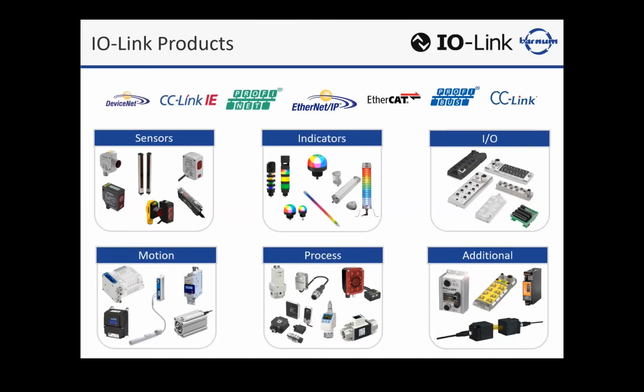So if we look at sensors themselves, having IO-Link capability allows you to program that sensor, set points, functionality directly from the HMI without necessarily a PC interface or changing your PLC logic. But also there's over 100 different parameters that you can monitor and check status on. For instance, if you're using a laser measurement sensor for position control, not only are you getting very, very finite information back from that laser distance sensor, but you're also getting tolerances back, such as, is the lens getting dirty? Wow. Do I need to do some preventative maintenance so I don't bring the line down? What's ambient temperature? What temperature of the sensor? All things that come into play during your process.